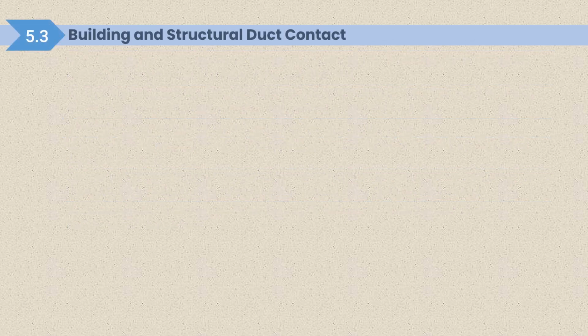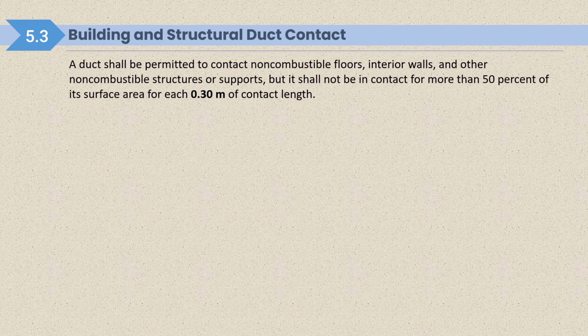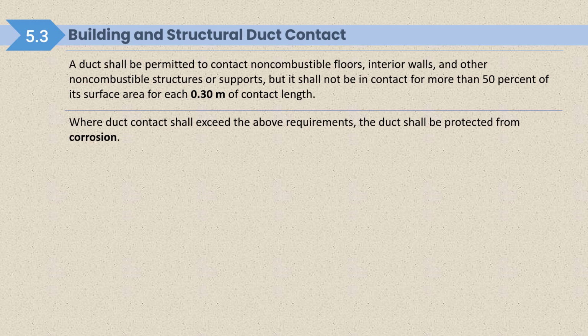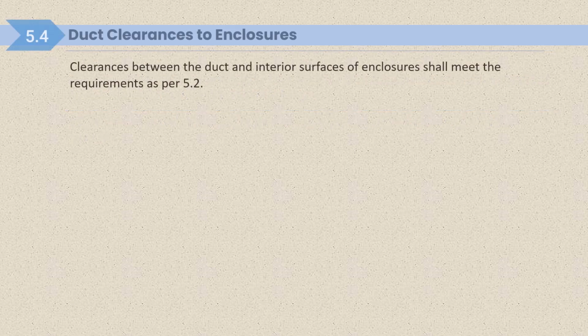In 5.3, building and structural duct contact. A duct shall be permitted to contact non-combustible floors, interior walls and other non-combustible structure or supports, but it shall not be in contact for more than 50% of its surface area for each 0.30 meter of contact length. So maximum 50% of the duct surface area can contact the non-combustible structure or support for each 0.30 meter of contact length. Where duct contact exceeds the above requirement, then in that case the duct shall be protected from corrosion. Duct clearance to enclosures we have already covered in 5.2.